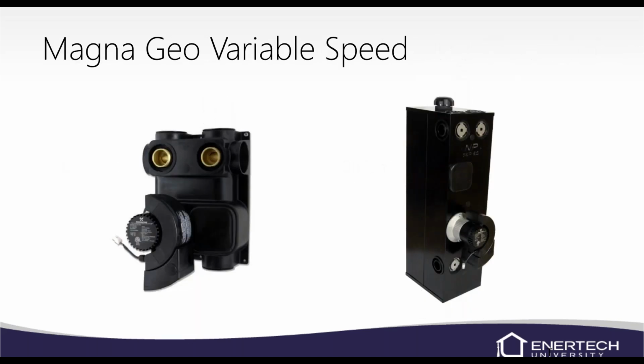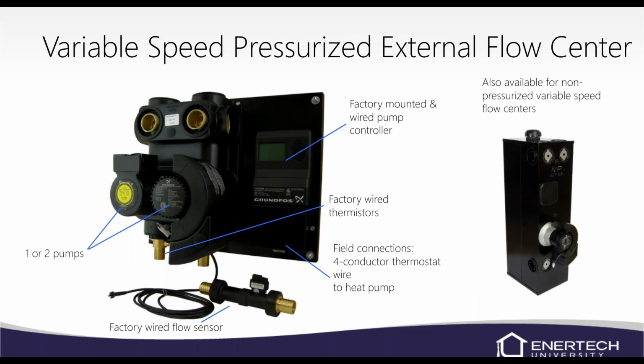We do have variable speed in the pressurized and non-pressurized flow centers now. And then we also have a variable speed with a fixed speed as your backup. So if you need more flow, it'll turn on that second pump. Basically, again, you can see a 2-pump here on the left side, and it does have a factory mounted and wired pump controller. It has thermistors depending on the type of setup you want. You can have just the flow sensor, or you can have flow and temperature sensors. And again, we have pressurized and non-pressurized variable speed flow centers now.